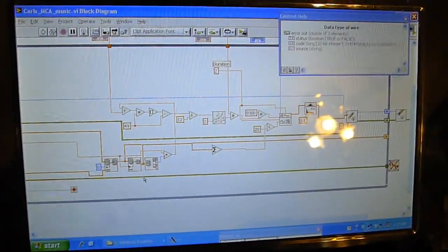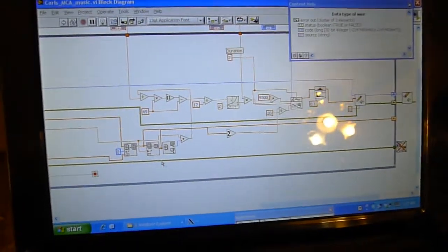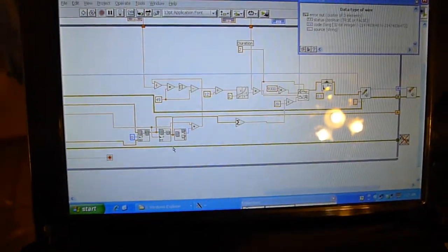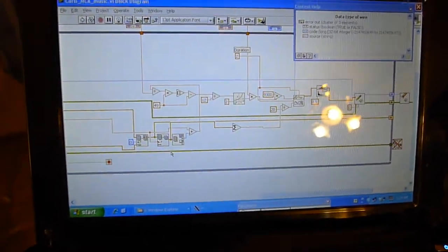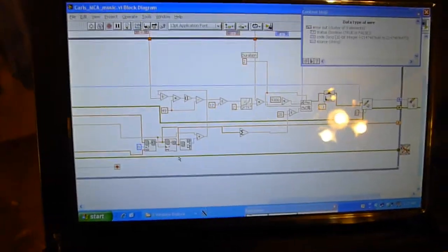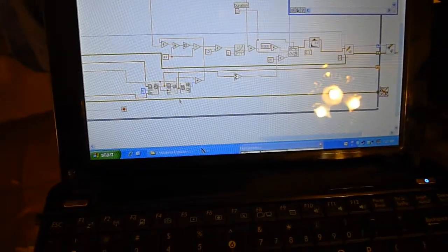This array, we search for the maximum value, in other words, what channel contains the most counts. And again, it's only a 20 millisecond spectrum, so there are likely to only be a few dozen counts in there, but some of those bins will have more than one count. In fact, some will have two or three counts. So we find out what channel has the highest number of counts.